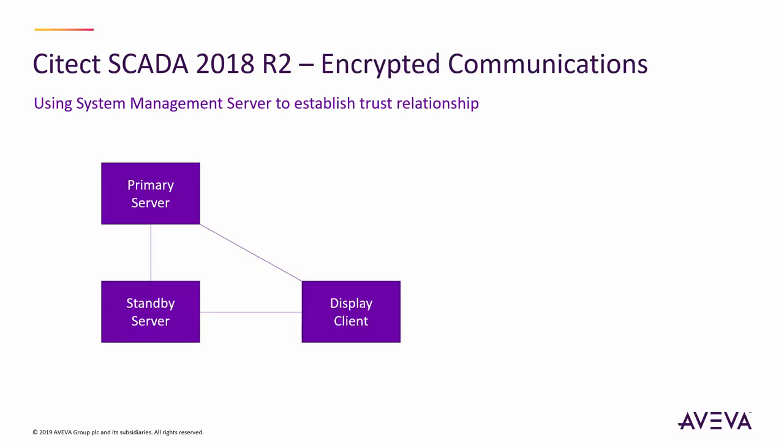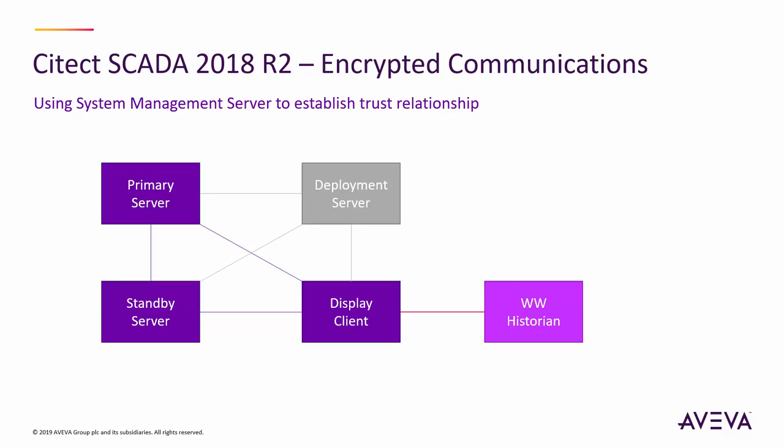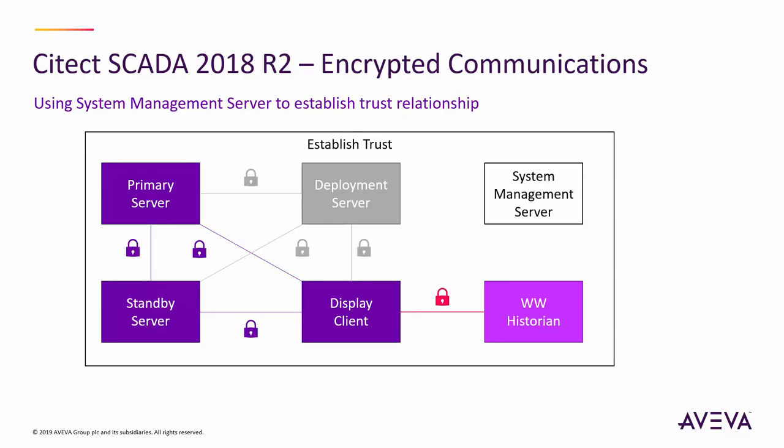By way of example, a standard redundant configuration with a primary and secondary server pair, a remote client, a historian, and a deployment server can now easily be encrypted with the addition of a system management server. This facilitates the creation and deployment of certificates to establish a trust relationship between all system nodes.